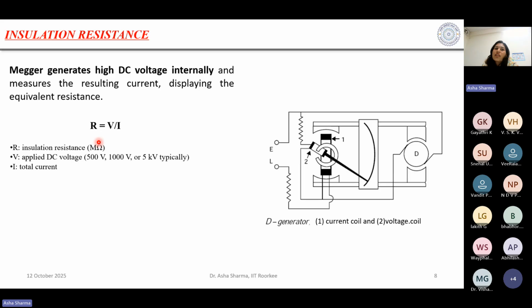First is insulation resistance. We are talking about insulating materials. In the overhead line insulator, one end is connected to the transmission line and the other to the ground, so it must have very high resistance to restrict current flow. The equipment used to measure this insulation resistance is known as the megger.